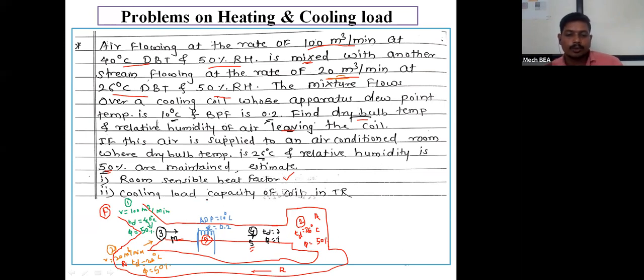And how to calculate the cooling load capacity of coil in terms of TR? So to calculate the cooling load capacity of coil, here point number 3 is the inlet point for the coil, and point number 4 is the outlet point for the coil. So based on point number 3 and point number 4, I am going to find out the enthalpy corresponding to point number 3, enthalpy corresponding to point number 4, and mass of air.